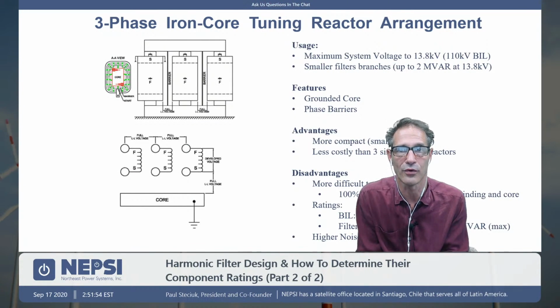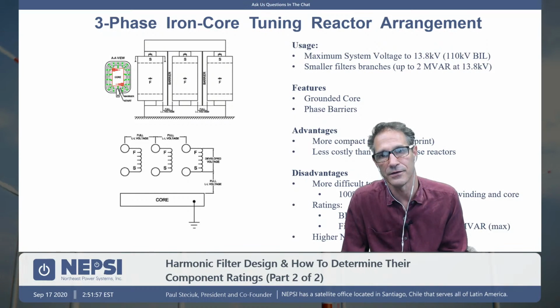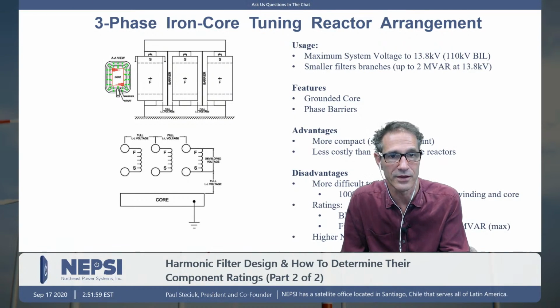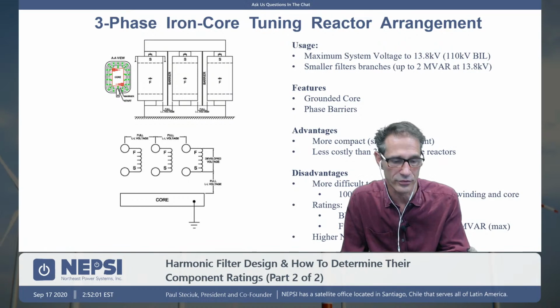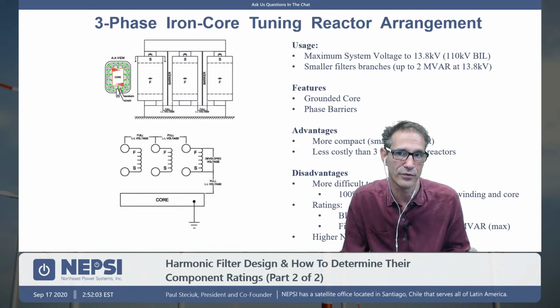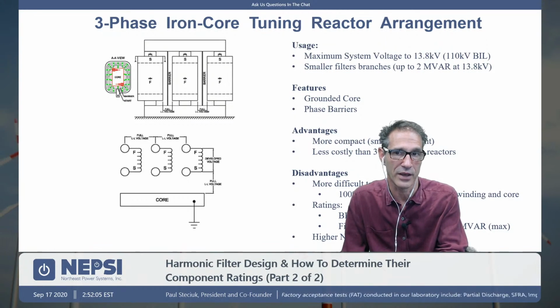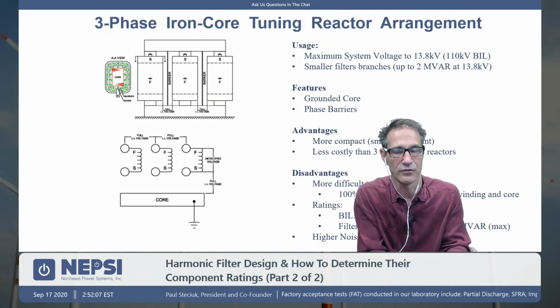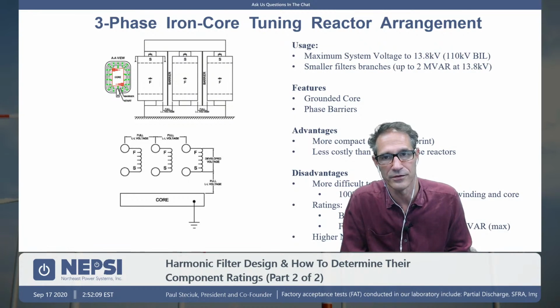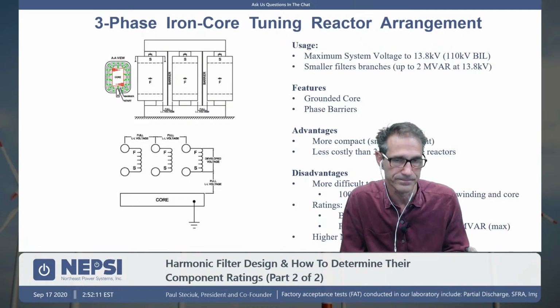Between winding and core, we have full voltage, and that means we're always stressing that insulation. It's really critical on the reactor supplier at that point to properly design that 3-phase reactor, because now you have full voltage across the winding to core insulation.